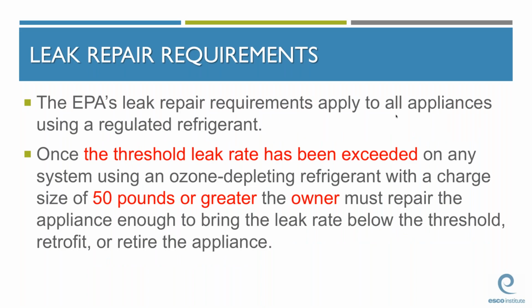So once the threshold leak rate has been exceeded on any system using a regulated refrigerant, the owner must have the system repaired to a point where the leak rate falls below the threshold. If this can't be done, the system must be retrofitted or retired. And this rule applies to systems with a total charge of 50 pounds or more.